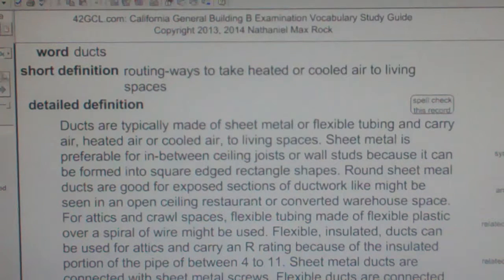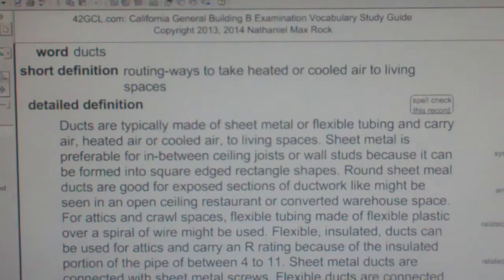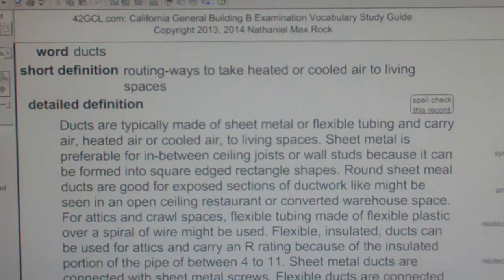Sheet metal ducts are connected with sheet metal screws. Flexible ducts are connected with plastic bonds or zip ties, and then the insulation is wrapped with sealing tape. Tape rated as UL 181 is to be used according to some codes, but butyl duct tape and oriented polypropylene, or OPP, duct tape is being used commonly now.